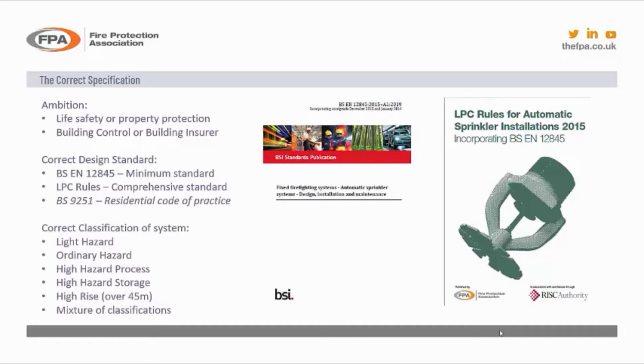Well, this will depend on the building and its use, its construction, its height and other factors. As we can see, there are many different types of classification of system. Light hazard limits compartment sizes to 126 square metres, and this would include offices, prisons and schools. In 30 years that I've been involved in fire protection and sprinkler systems, I've never actually designed a light hazard sprinkler system.